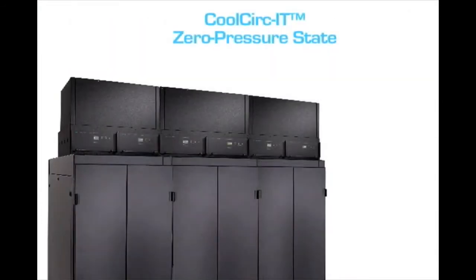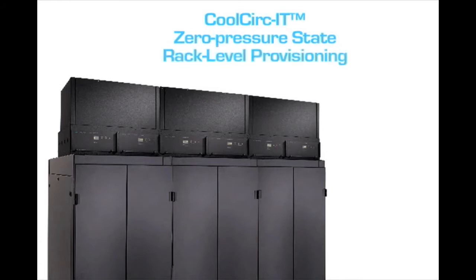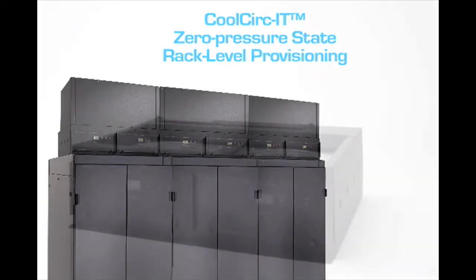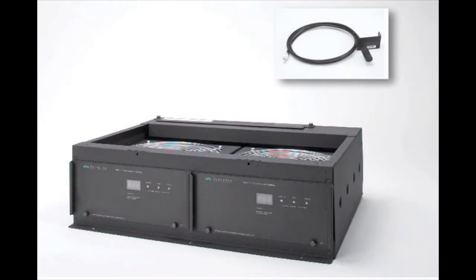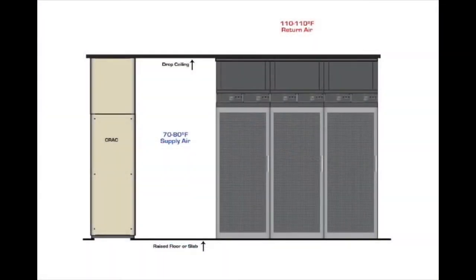The rack maintains a zero-pressure state to prevent leakage, and the system's feedback gives users the ability to provision equipment at the rack level based on that rack's existing load, saving time while reducing the risk of equipment failure. The pressure-controlled units utilize a pressure sensor located at the back of the rack to control the required air volume necessary to cool the equipment. CoolCirc-IT units, which do not require additional piping or mechanical systems to install or maintain, dynamically scale airflow to match the cooling load of the equipment in the rack.